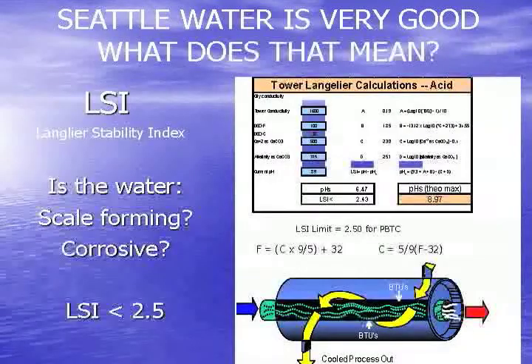So what does that mean? Well, when you look at water's ability to either be scale-forming or corrosive, there's a couple models in the industry. I'm going to use LSI for the purpose. This is basically the Langelier Saturation Index. It takes things like calcium, alkalinity, conductivity, pH, puts it in a model, and predicts whether the water is going to be scale-forming or corrosive. We can change that model. If we cycle up the cooling towers, we actually have different numbers. As we go up the LSI scale, we get more scale-forming. As we go down the LSI scale, we get more corrosive. Most water treatment programs can handle an LSI of 2.5. Once you exceed 2.5, the chemistry itself really can't handle all the calcium and alkalinity in the water. You can still scale on top of it.